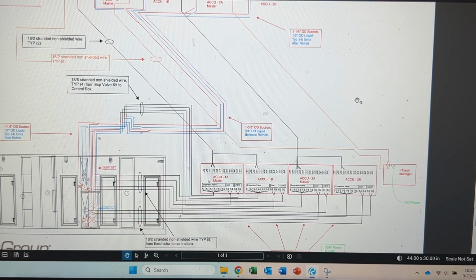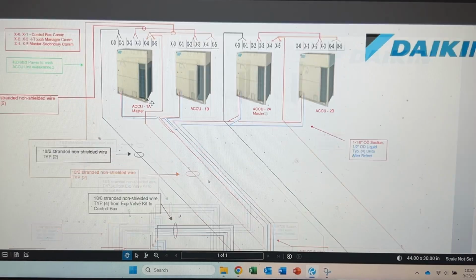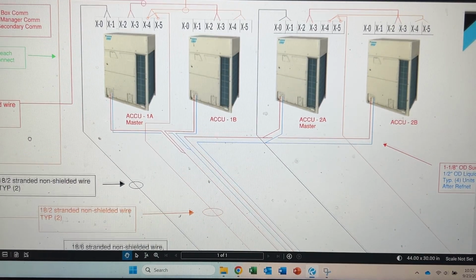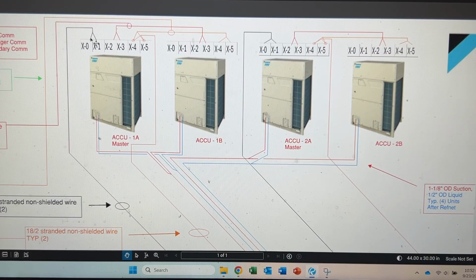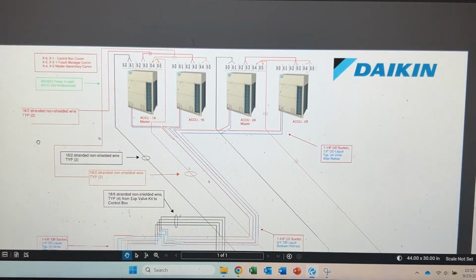All right, so I'll do the wiring here first. We talked about the refrigeration piping - the wiring here shows what the terminals are on the outside equipment, and how I illustrate what's got to tie to what. So I get it sized, and I think for the most part everything here is 18-2, stranded, non-shielded wire, with the exception of our expansion valve kit. So we'll do the outside equipment, and then I'll talk about this.